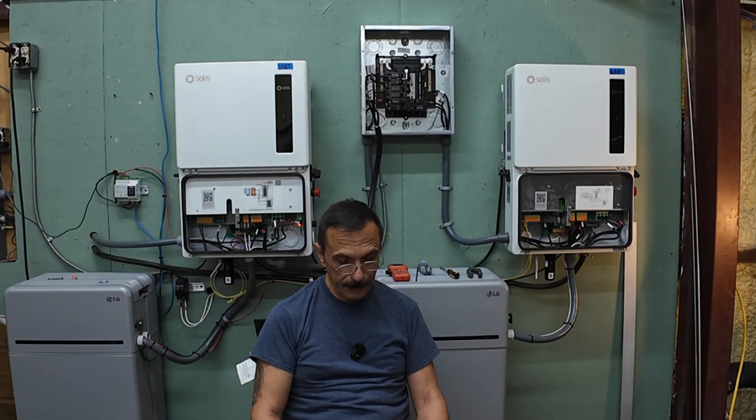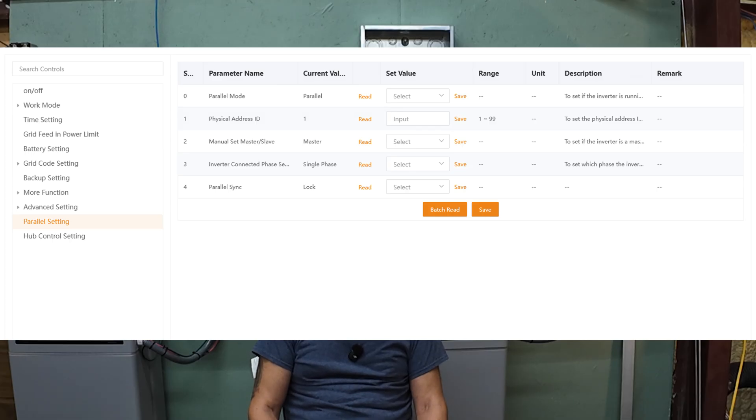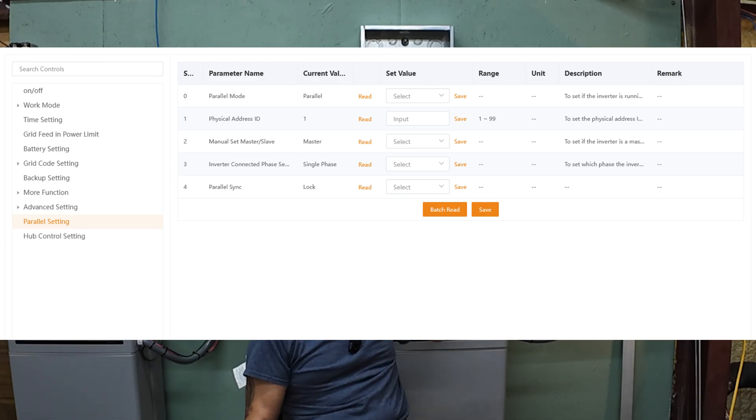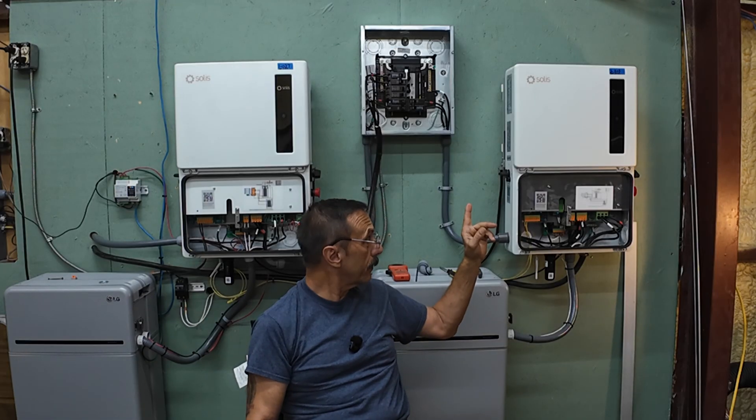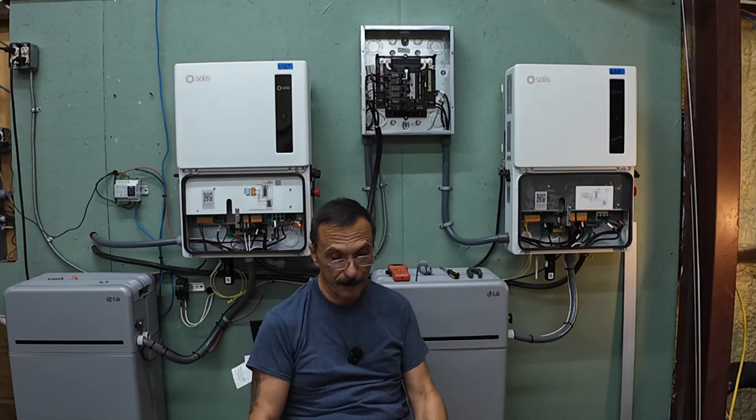Set the parallel sync to lock. After all slave inverters are set, configure the master inverter. Connect to the master inverter via the Solis cloud app. Navigate to parallel settings. Set the address ID to one. Set the manual master-slave setting to master. Set the phase setting to the correct configuration. Set the total number of inverters and set the parallel sync to locked — this will automatically push the master's parameters to all slave inverters. One thing to say before you begin: make sure the configuration is set up exactly the same on both inverters.